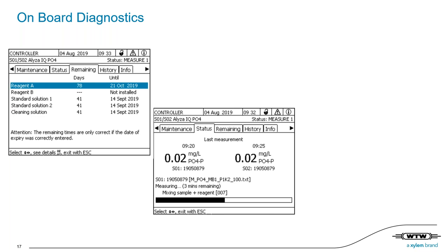Okay, and a follow-up question regarding the saline solution. Is there a limitation on the component material, but not on the measuring principle? For the measuring principle itself, I will check again what the limitation is for the salinity, as I mentioned before. But one important point is the material, as you will get corrosion. For example, for the IQ SensorNet, we have the normal sensors, which are made of stainless steel. And for salt or salinity and saltwater applications, we have the so-called seawater versions, which have a special plastic material and titanium heads. So this is really a different material as well.